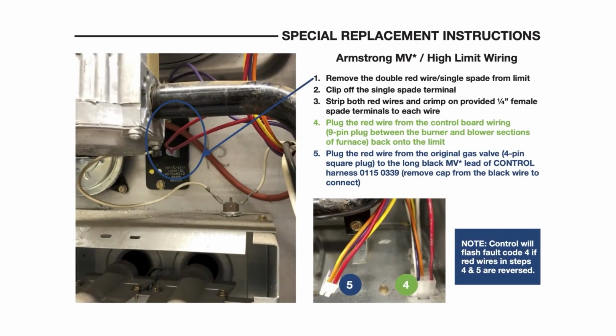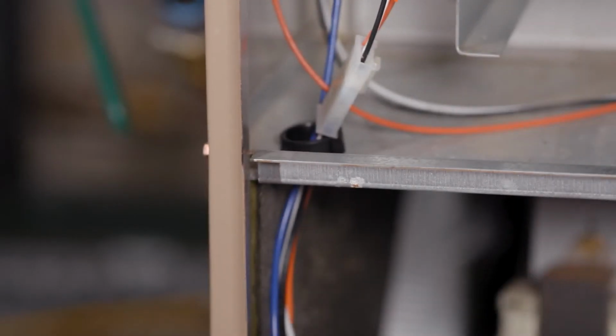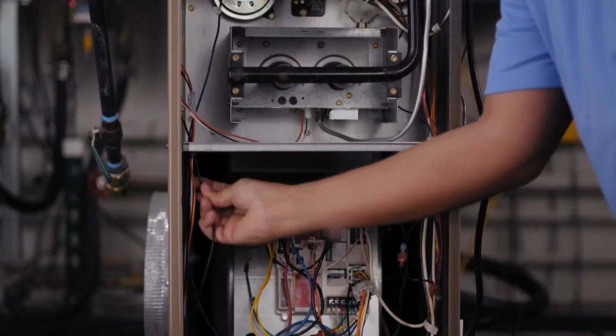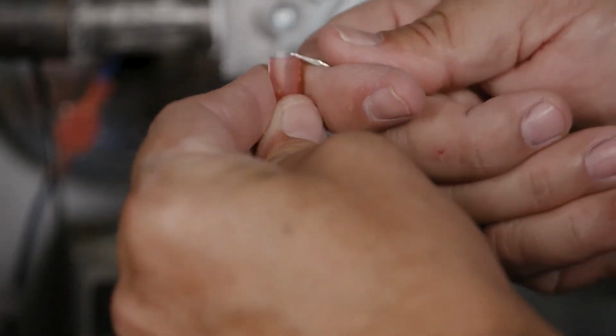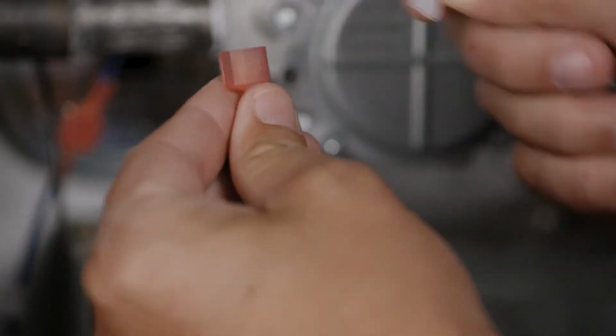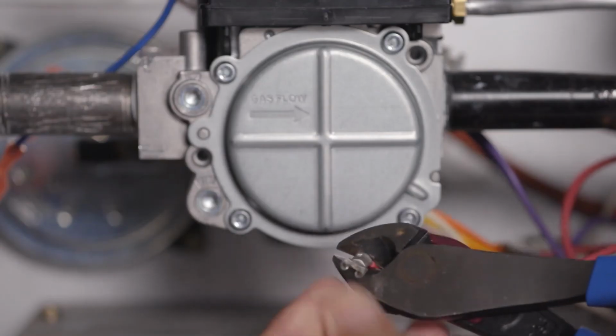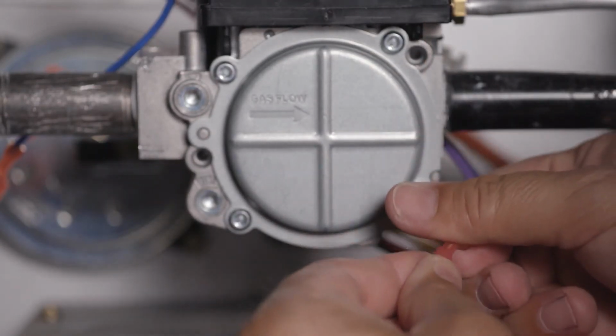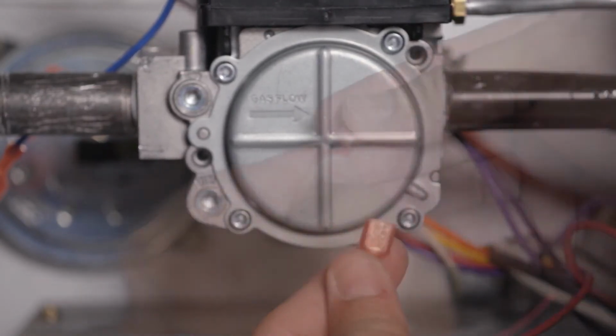For Armstrong furnace applications, special replacement instructions are included. For this type of application, the black MV wire attached to the 12-pin control harness will be used. Route the black MV wire from the control board to the gas valve area. Remove the plastic cap from the MV spade terminal. Next, locate the main furnace limit and remove the spade that has 2 red wires connected to it. Cut the spade off and strip both wires. Crimp the provided 1/4" spade connectors on each wire.